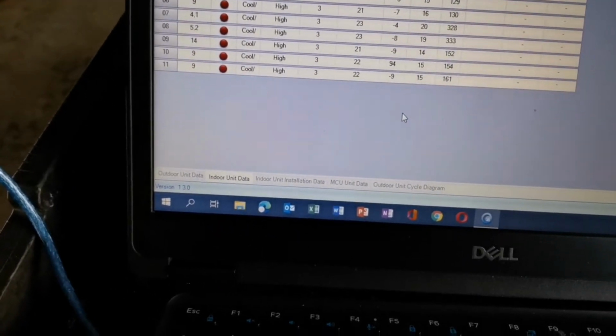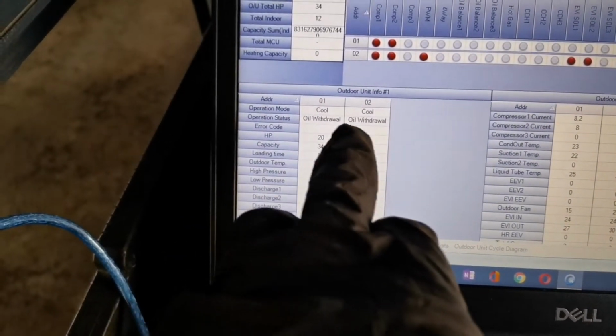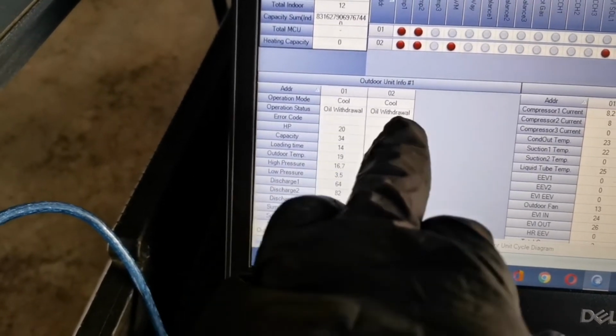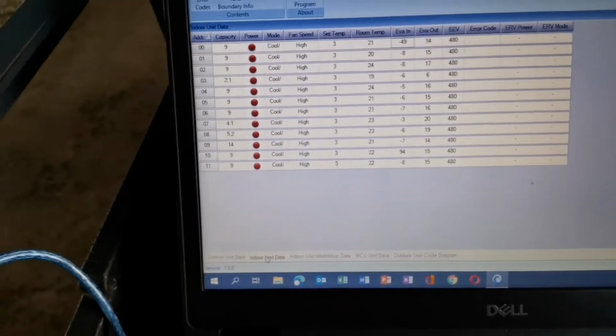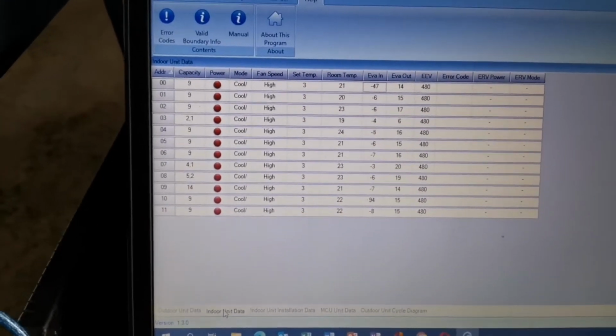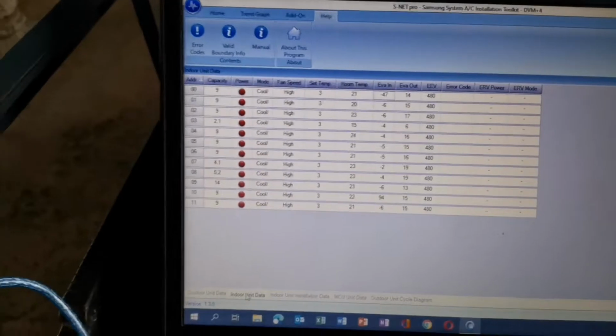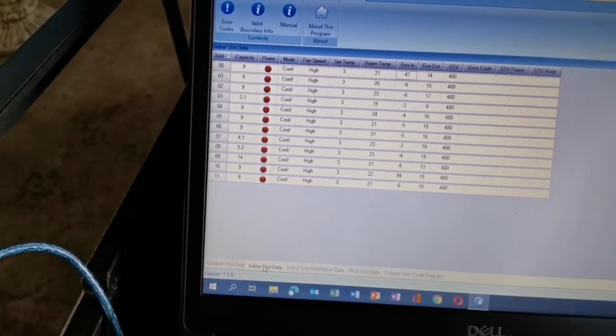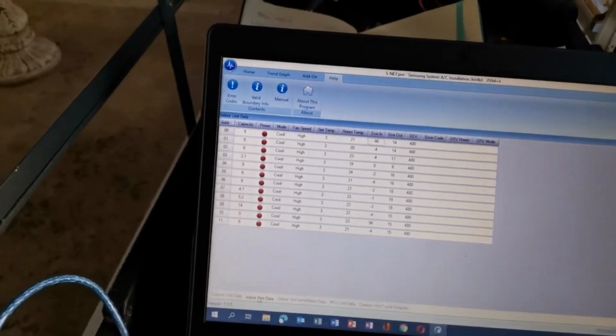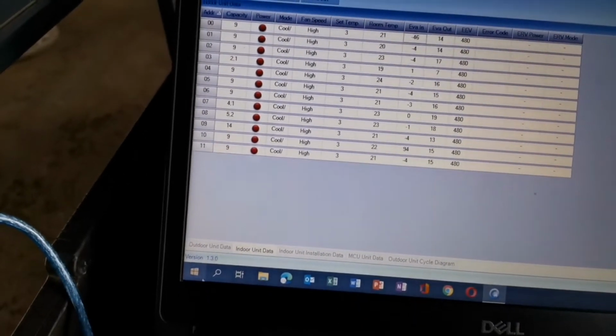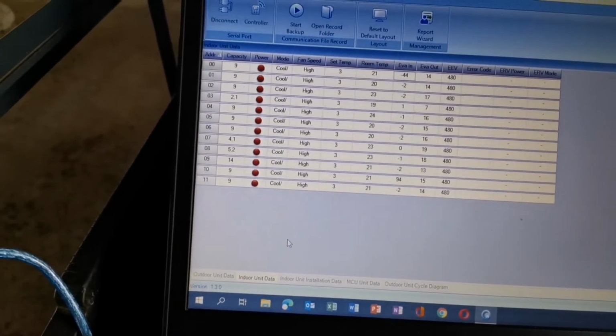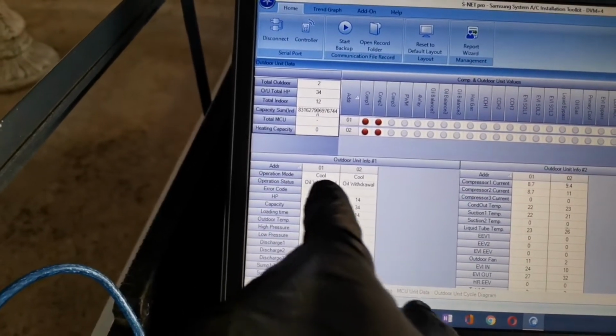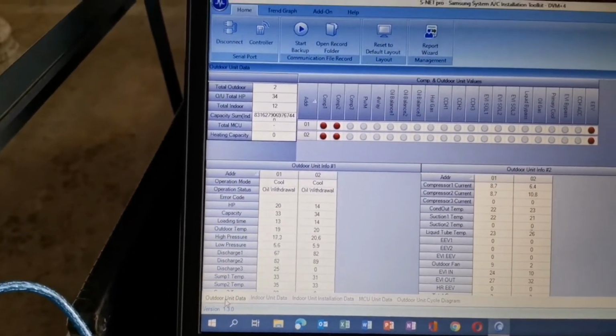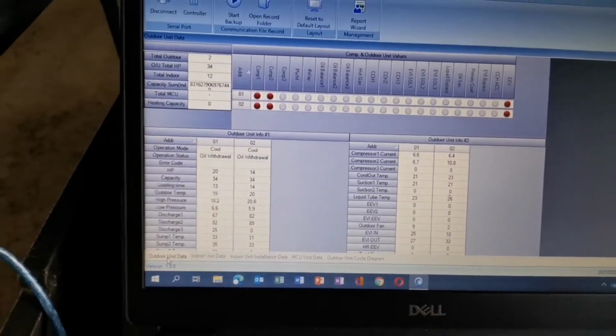I'm going to allow the system to come out of safety start. Let's see, okay, it's on oil withdrawal right now. Once it's in test operation, these numbers should start stabilizing, and that'll give me a more accurate display of where we are with the sensors. If we've got sensors that are heavily out of range, right now I can see 2 sensors that are out of range. It'll be address 10 and 00. The rest of them, as you can see, the system's starting to stabilize, as temperatures are coming into the positives. So yeah, like I said, let's wait till this is in normal operation, and then we will have a look and see what our temperatures look like.